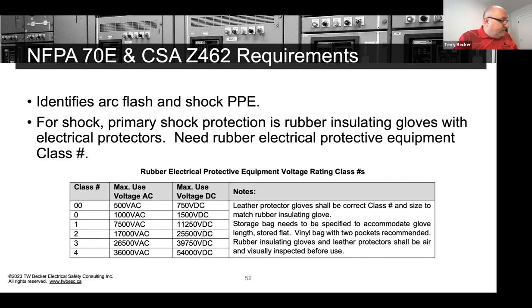They're meant to be holding the probes on your test instrument when you go in, and then no inadvertent movement, because I'm going in bare hand, or with the glove now. So this is it for shock. Get these gloves if your workers are doing energized work and their hands go inside a box with electrical equipment, 120 volt AC single phase or higher, and then with inadvertent movement, they won't get shocked.